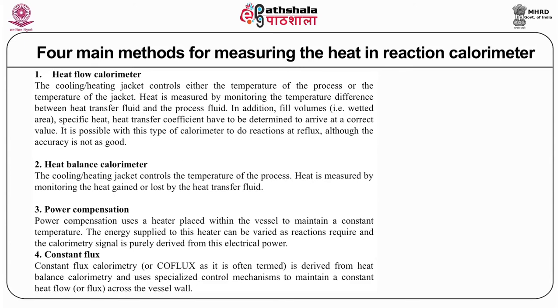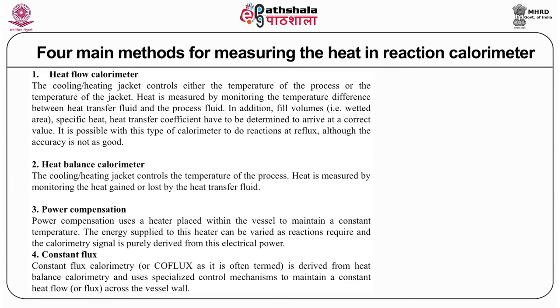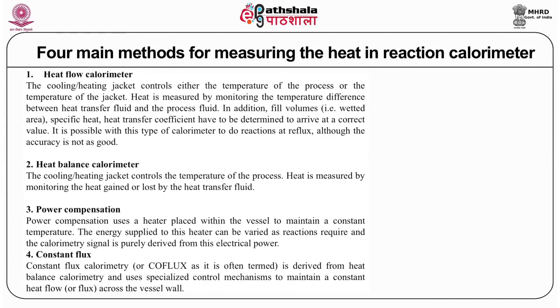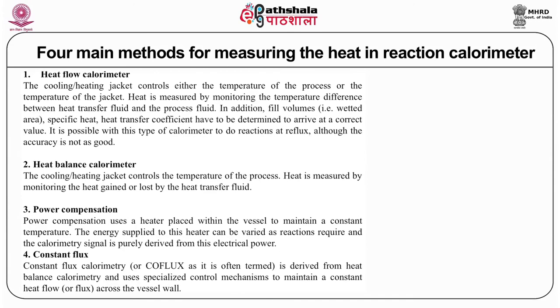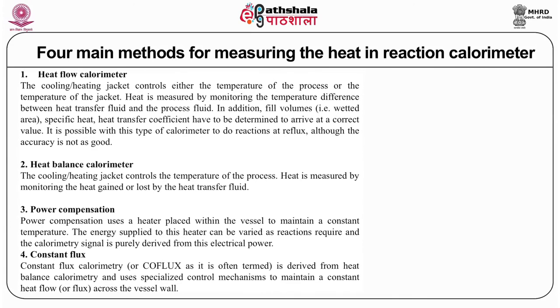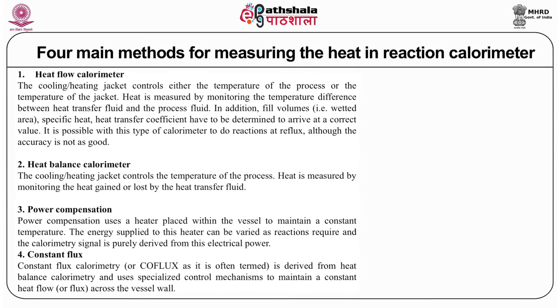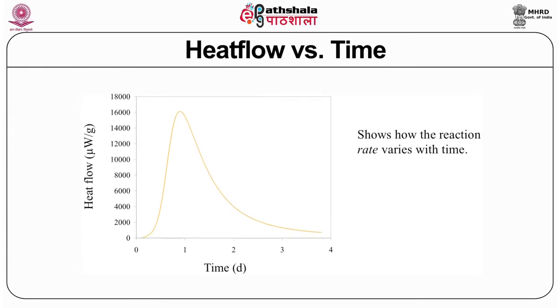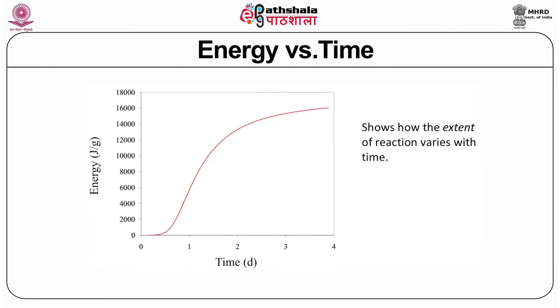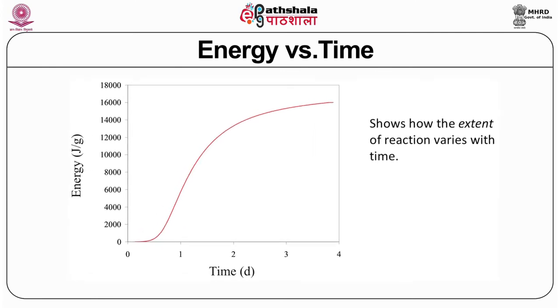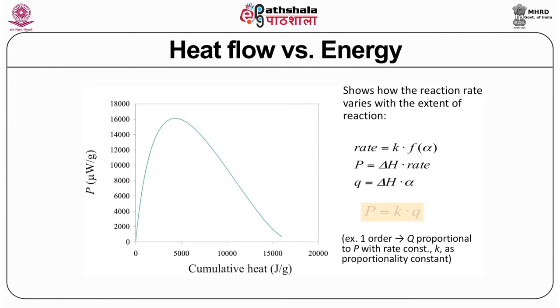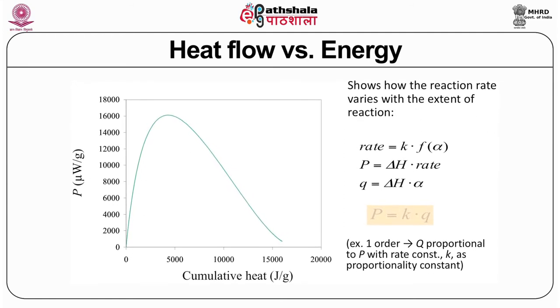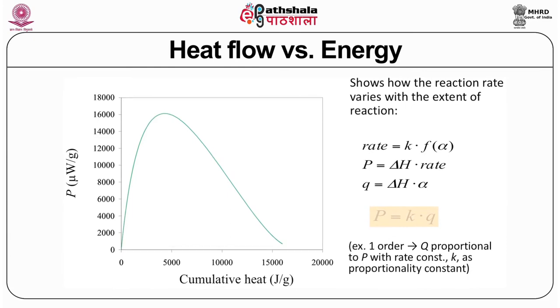The fourth type is constant flux calorimetry, also called co-flux, which is derived from heat balance calorimetry and uses specialized control mechanisms to maintain a constant heat flow across the vessel wall. It tells you how heat flow changes with time, showing energy versus time and heat flow versus energy. This can be expressed as P equals K times q, representing a first-order reaction.